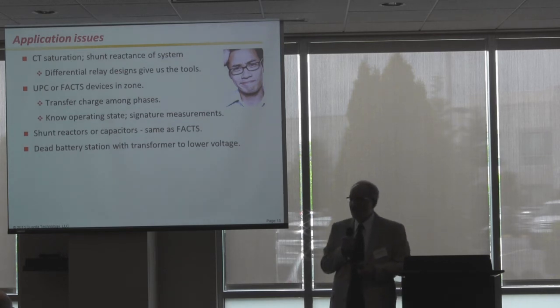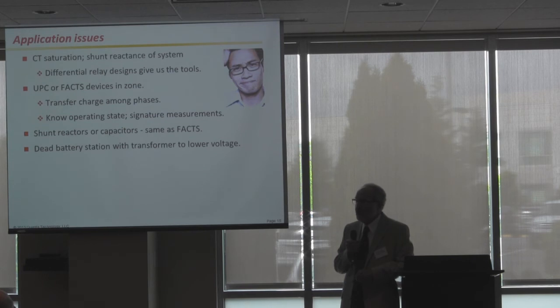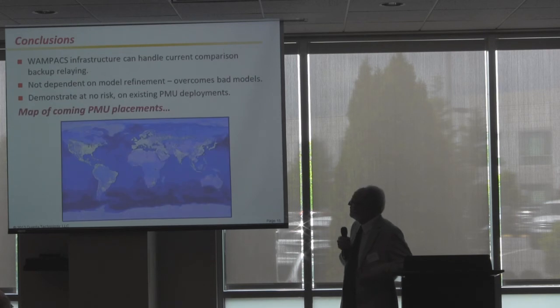Same thing with shunt reactors and capacitors that are also fault-like leaks in and out of the zone we're protecting. Protection engineers looking at backup protection are always worried about that so-called dead battery station, for which we want our zone 3 relays to look without analyzing the whole problem. There will be some compromises in the scheme when we do that, but it knows when it's lost its data from a dead station, and there are things we can do.